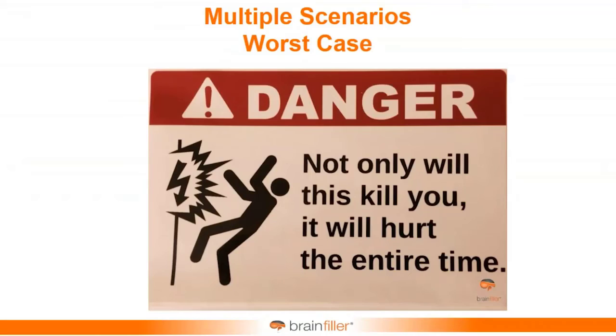Another strategy, and many would use this, is they would just look at it maybe from a legal perspective. Well, let's just put the worst case out there. And they would just have one label, and it would be based on the worst case scenario. Well, the problem with this one is worst case may be based on some very limited scenario that happens maybe once every couple of years, or maybe it's just so infrequent. But if your labeling strategy is based on that scenario, now you may think of it as like a penalty for your PPE because it's based on this worst case strategy. Others have actually opted to just have labeling that'll have the PPE based on normal configurations only.